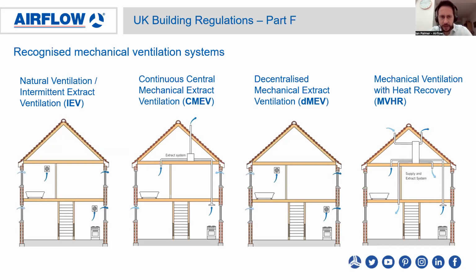Decentralized mechanical extract looks very similar to natural ventilation with intermittent extract. The only difference is that these fans run continuously. Whereas intermittent is on and off, these fans run continuously. Finally, at the end there, you've got mechanical ventilation with heat recovery. This will do the full supply and extract of the entire building, and the system does not need to rely on trickle vents or opening windows and doors.